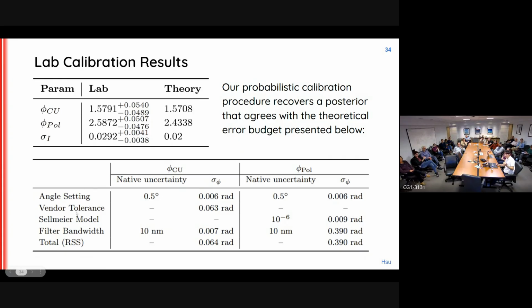And likewise, because the polarimeter is a 633 nanometer quarter wave plate, but we're operating at 670, we need to use a Sellmeier model to look at the error, I believe, in the birefringence itself. Okay, and that turns out to be pretty small as well. But because we have a finite filter bandwidth of 10 nanometers, we put a filter in front of the light. That actually causes a huge uncertainty in the polarimeter because we use a multi-order wave plate. So a 10 nanometer change in thickness, that's many waves thick. Okay, and that actually introduces a 0.39 radians uncertainty on the retardance angle for the polarimeter.